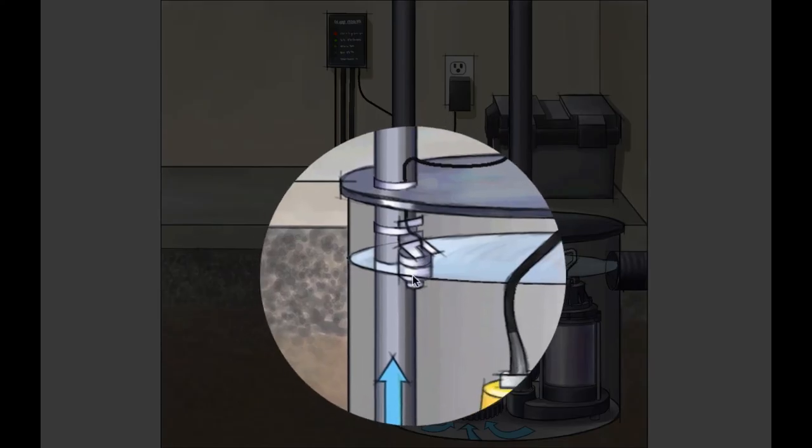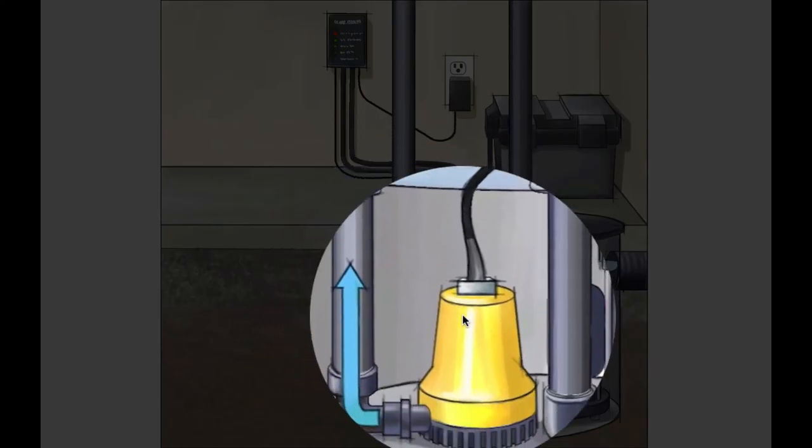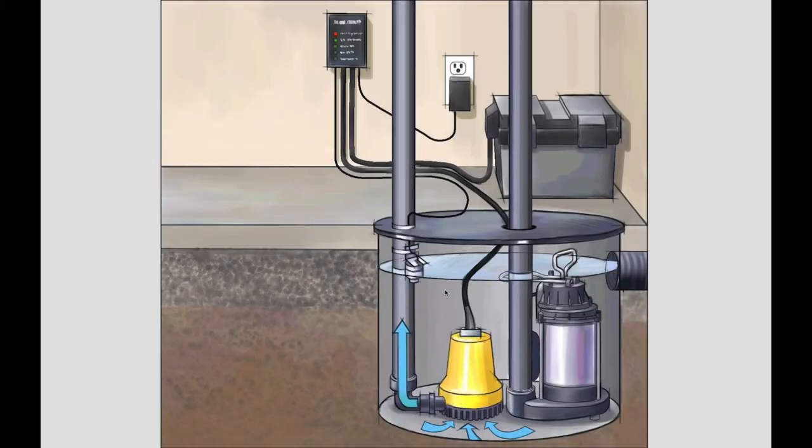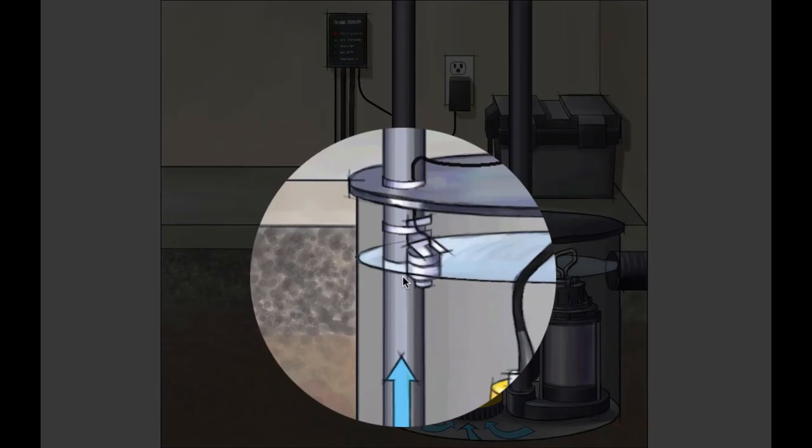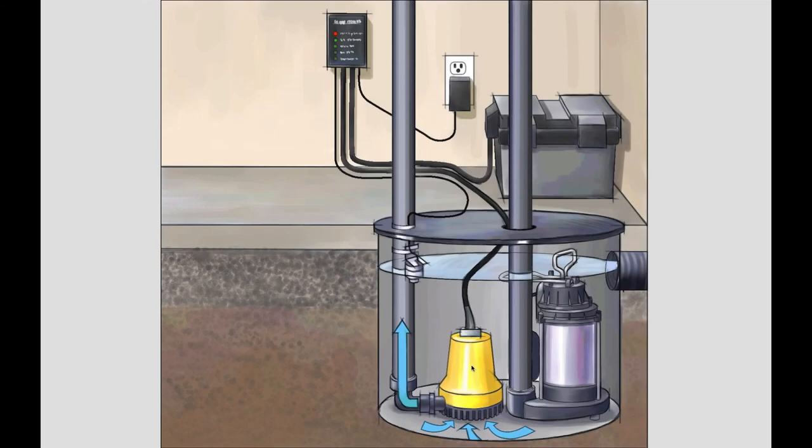So this battery pump's not going to come on until the water level rises, in this case, to that spot here, which is quite a bit higher than the activation point of the other pump. But the idea is that this really is a backup. So it won't come on unless the power goes out and inactivates the other pump. It will also come on if the other pump fails. So it gives you a lot of extra protection, which is what you need.